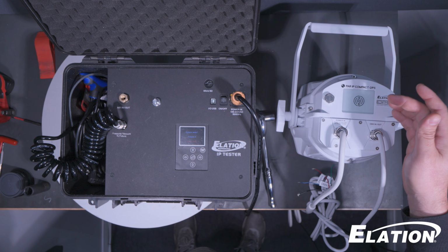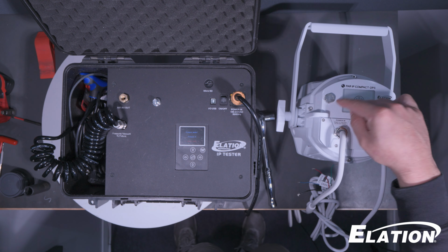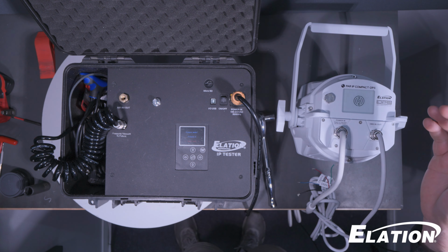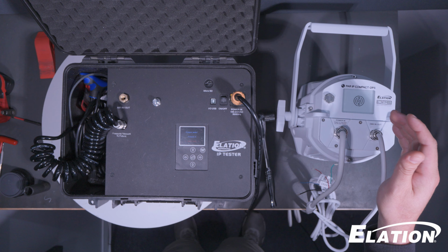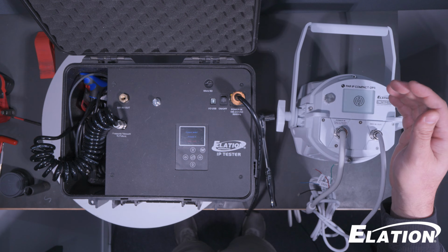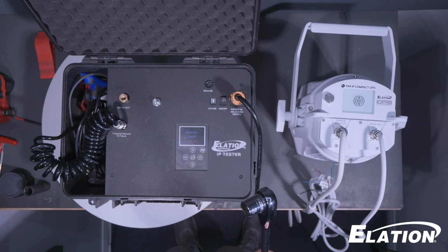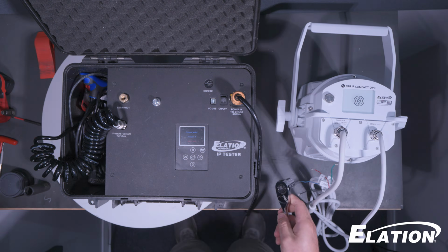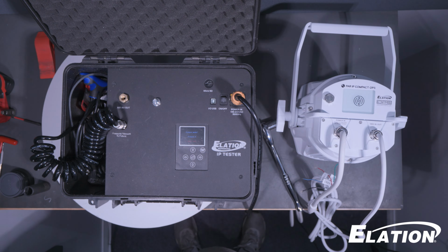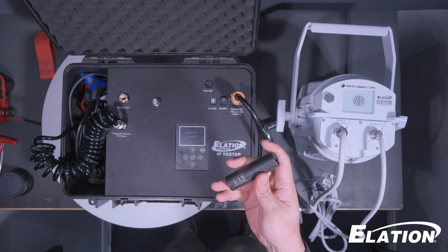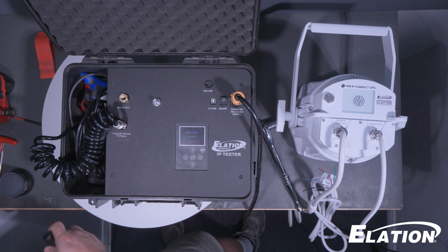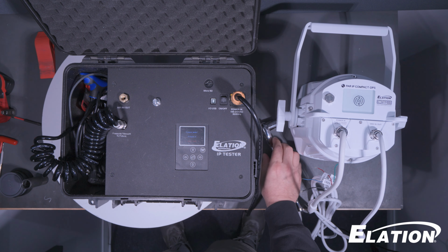The first thing that we're going to want to do is take off this valve. Sometimes you could do it by hand. Sometimes you can't. You're not supposed to have it very tight anyways. But if you can't do it by hand, then you could go ahead and use a 16 millimeter socket. In this case, this little shorty is going to work fine. Depending on what unit you're working on, sometimes you're going to need something a little longer. It just depends on the unit. But in this case, we could just use the shorty. So let's take off the valve.